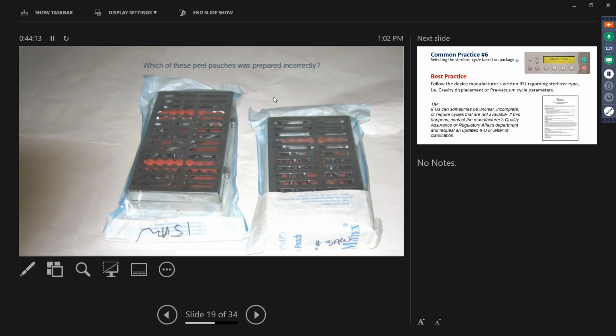You see what that means? Ripped it off and come up here. So they got bellows on the side. There's no way that would pass shelf life sterility testing. But we see that happening all the time.